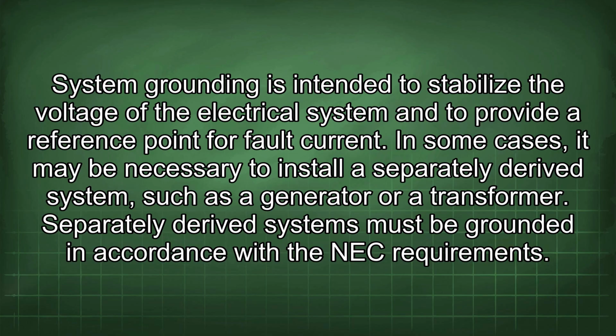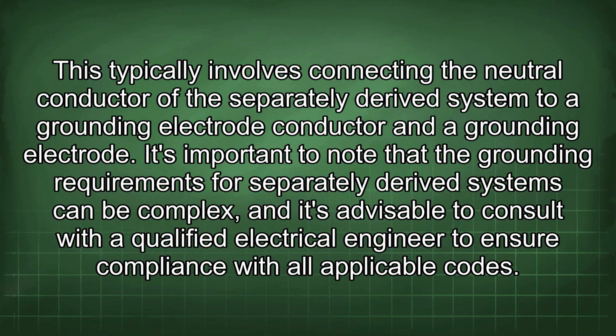In some cases, it may be necessary to install a separately derived system, such as a generator or a transformer. Separately derived systems must be grounded in accordance with the NEC requirements. This typically involves connecting the neutral conductor of the separately derived system to a grounding electrode conductor and a grounding electrode. It's important to note that the grounding requirements for separately derived systems can be complex, and it's advisable to consult with a qualified electrical engineer to ensure compliance with all applicable codes.